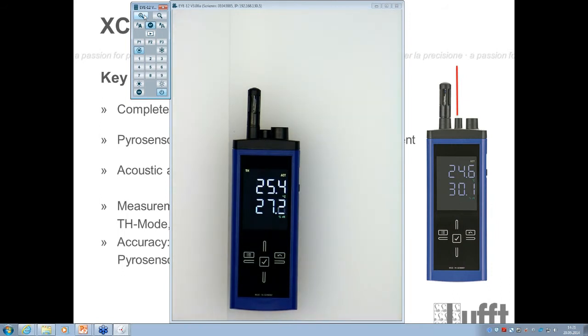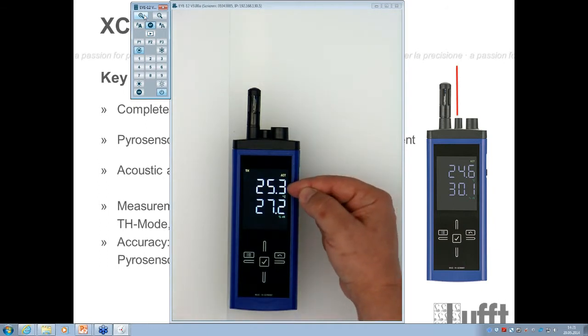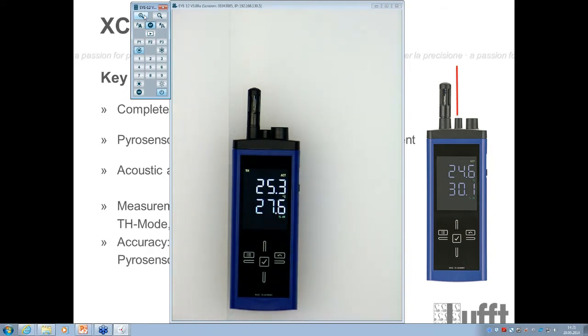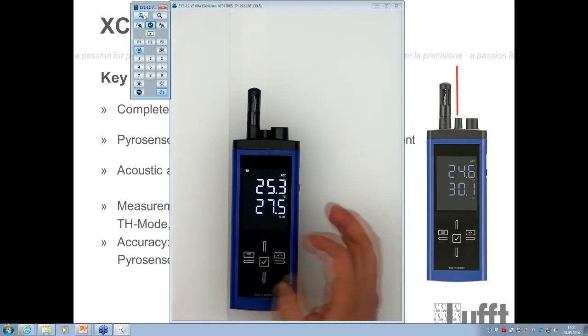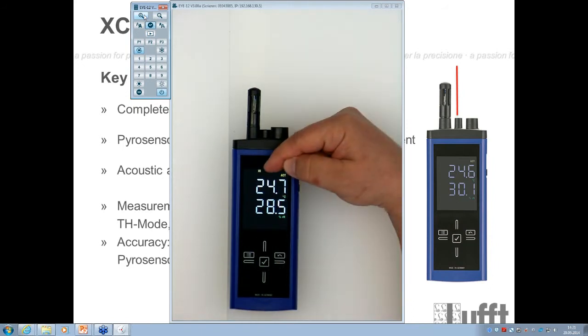So this is the TH mode you see here. It's nothing else than the same mode like the XC200. You will be able to show the temperature in this segment and the relative humidity in this segment. You can switch, of course, also between Celsius, Fahrenheit, and you can also activate the mixing ratio and the absolute humidity. Also all the same thing like for the XC200. In addition, you can switch to the IR mode. So we will do that now together with this button, with the up button here. So now you see IR is active.